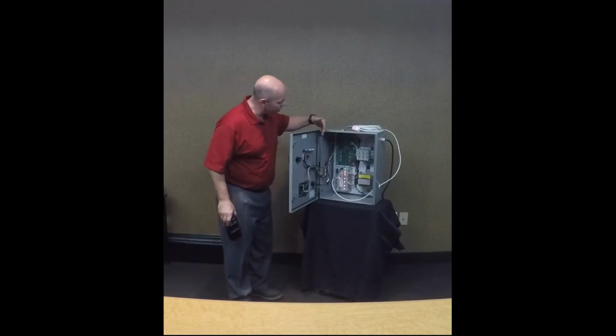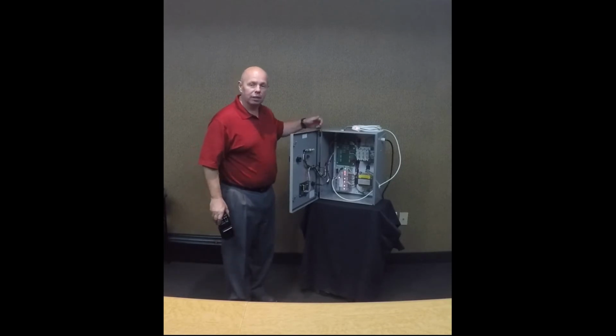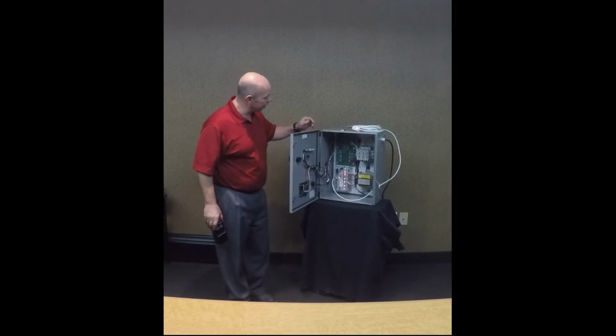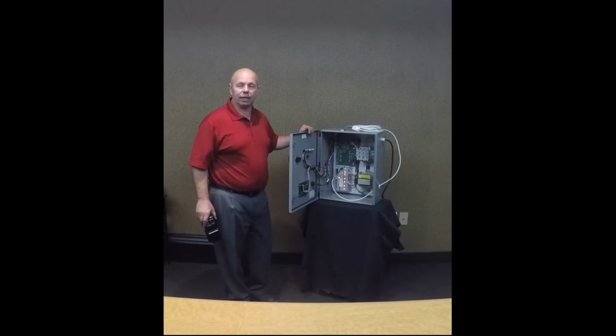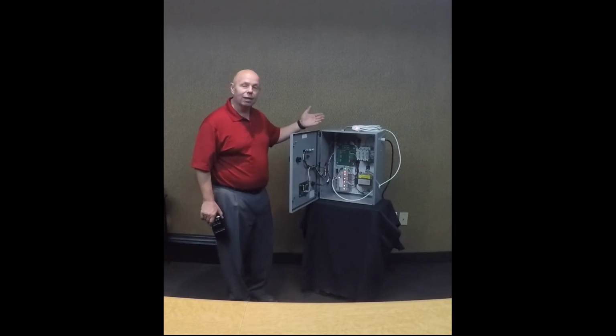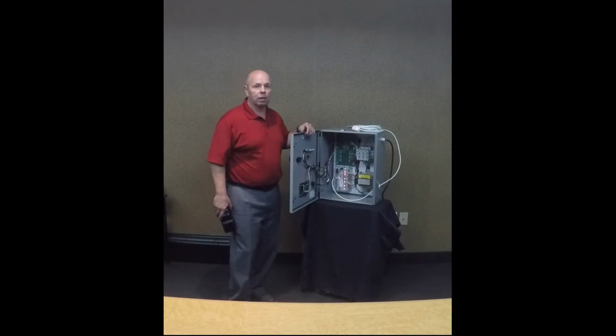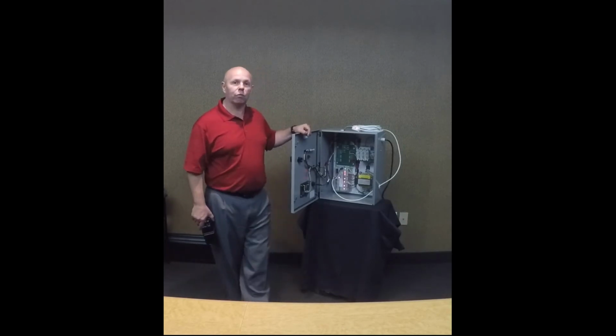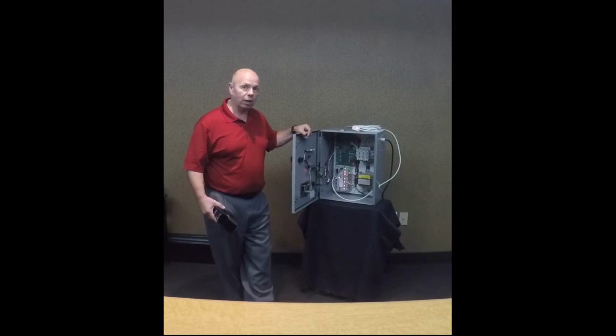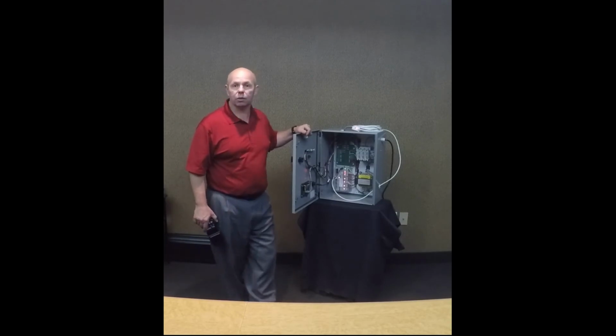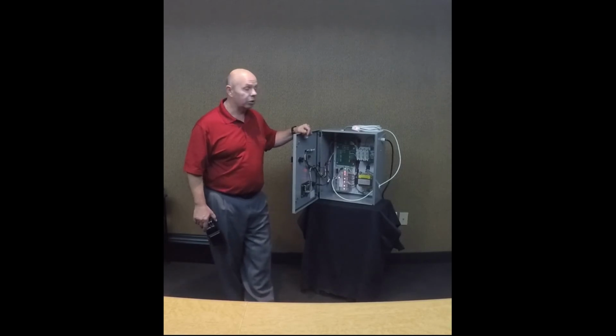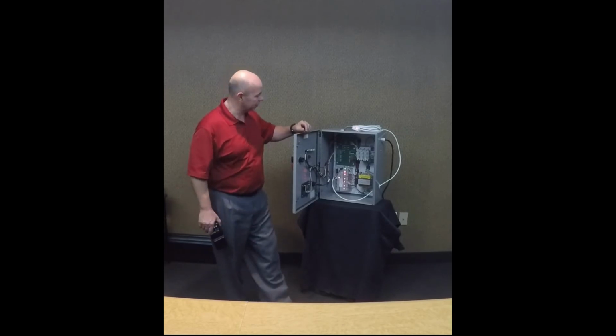The signal goes off. I'm not sure if everybody heard the clicking of the relay inside, but the relay has been activated and a signal has been sent out to the shunt trip mechanism of the circuit breaker, thereby tripping that breaker. Most breakers will trip within 1 cycle, but for any of the studies that we do, we recommend that you use a little bit longer, 30 to 50 milliseconds, to make sure that you have sufficient time in there and a conservative value for your incident energy.